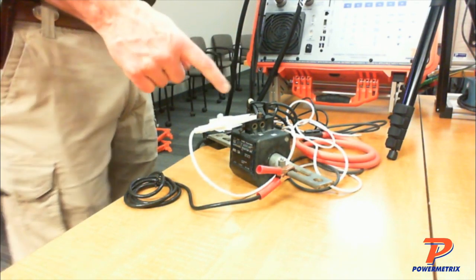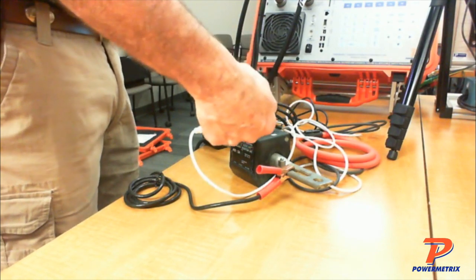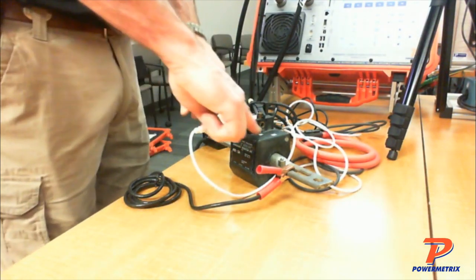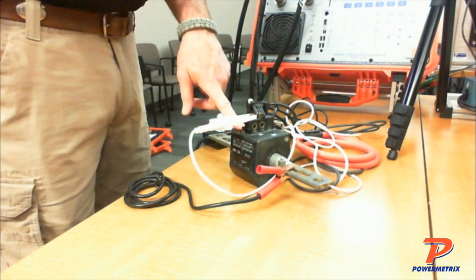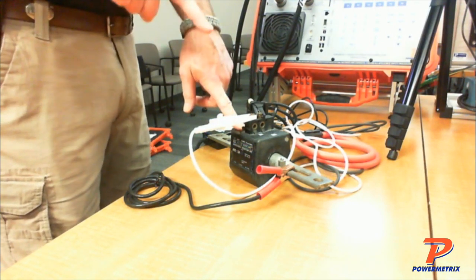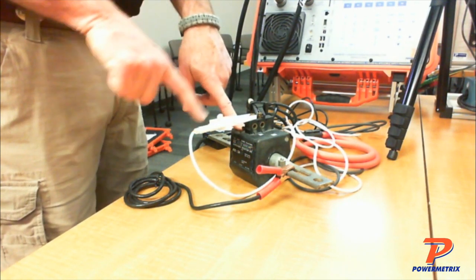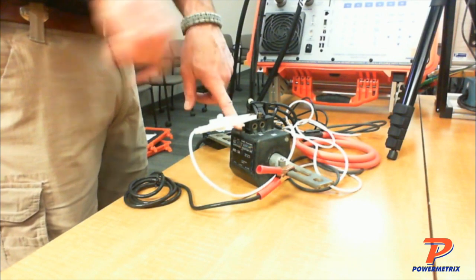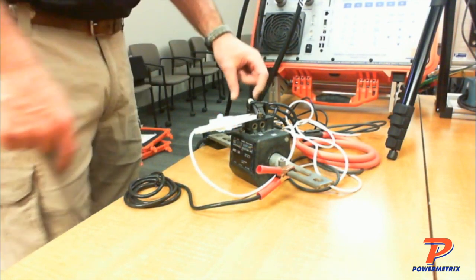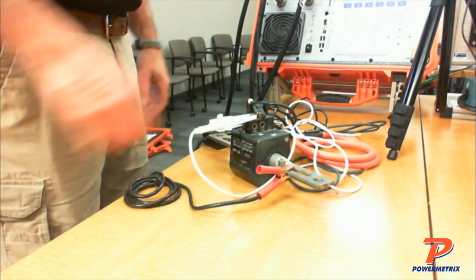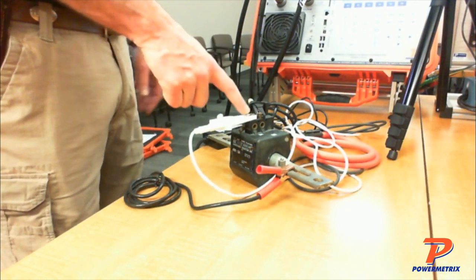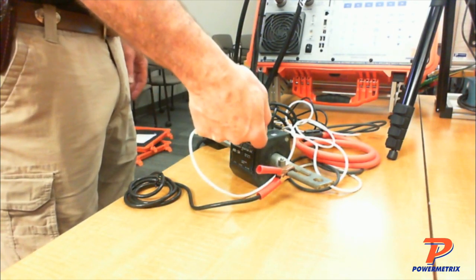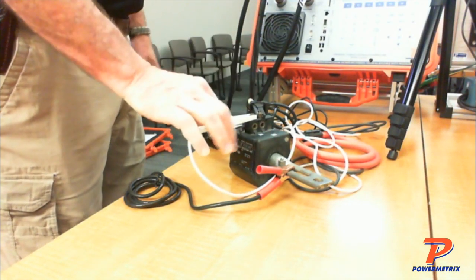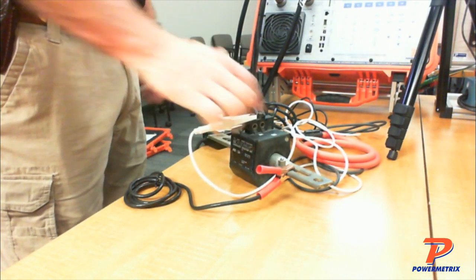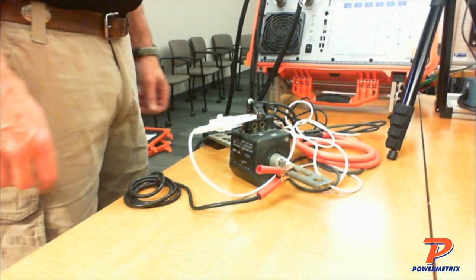So that means where people get these connected backwards on here is, I'm coming out of X1, so that's where my current's coming out, right? So if my current's coming out of here, remember, it's in the white, so I want the white alligator clip to be over here on X1. A lot of people see drive on that black and they stick it over on X1 and they get polarity reversal. You just got to remember the flow. We're coming in the white, which means I need to come where it's coming out of that CT and make my connection there. So I've got my white on X1 and my black over there on X2.